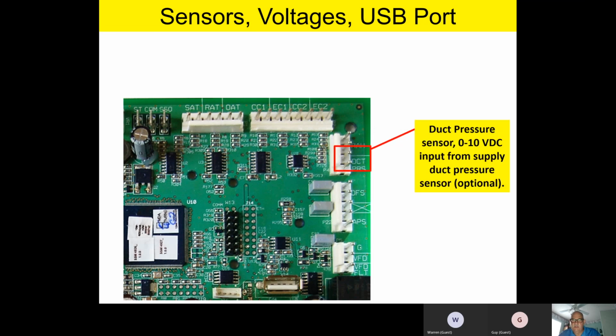Right down below that is another input. It's a duct pressure sensor, an input from a supply duct pressure sensor, which again is optional. So if you have a requirement, a particular architect or engineer building requirement where you have to have a duct pressure sensor, this is where you'd hook that up.